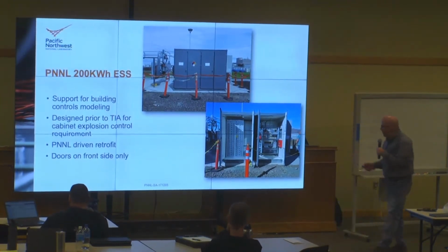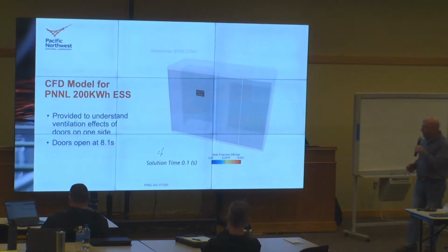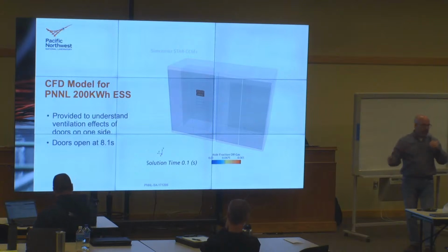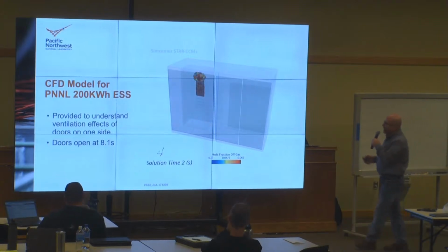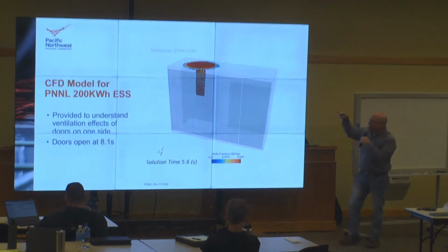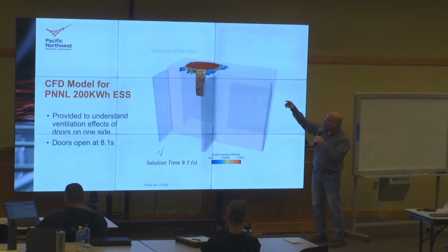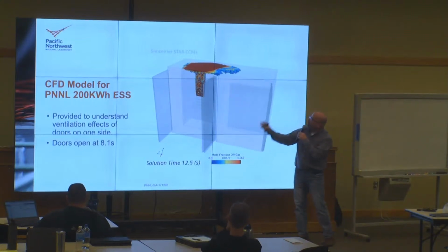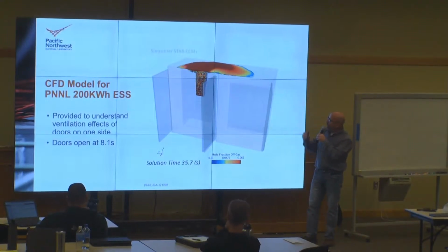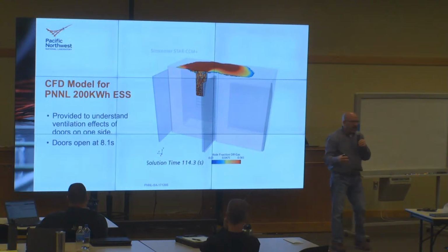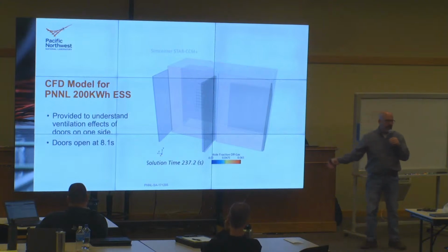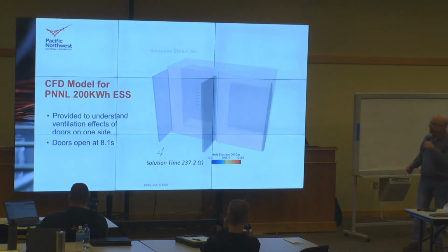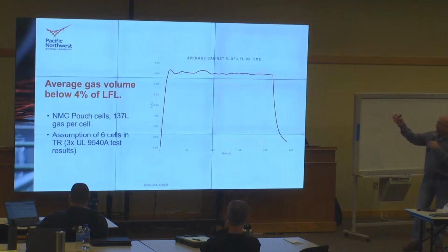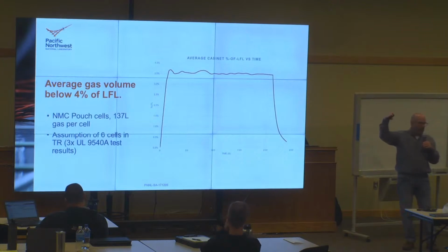To answer our question about whether it would work with doors only on the front side, we did a CFD model using data from the UL 9540A tests on how much gas evolves out of it. What we see is at about 8 seconds we have to trigger the doors, and at the top of the plume you're up at 25% of the LFL, but nowhere else. So the doors opening just on the front keep the entire cabinet well below the LFL, making it an effective way to provide deflagration prevention on our own battery. The average cabinet percentage was below 4%, while the code requires staying below 25% of the lower flammability limit, so we were well below that.